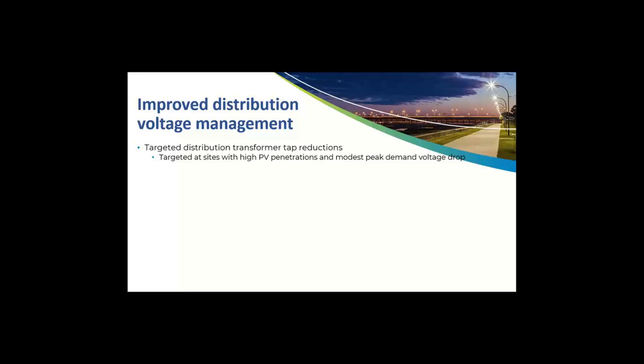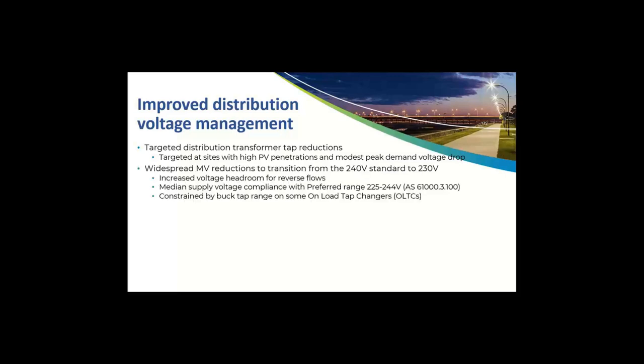So they're the transformers on the street level, which supply low voltage to customers. And where there's high PV penetrations and modest peak demand voltage drop, we've been able to lower taps. At the MV level, we've done widespread reductions, and that supported the transition to the 230 volt standard. And it's also increased the headroom for the reverse flows from PV.